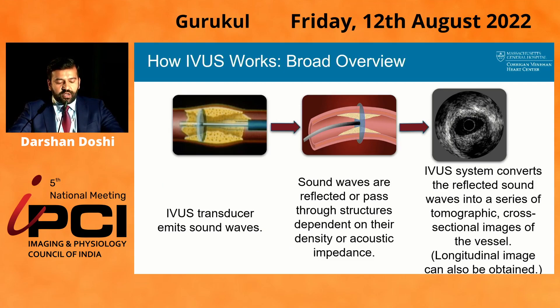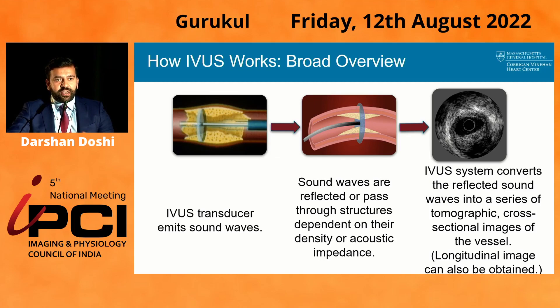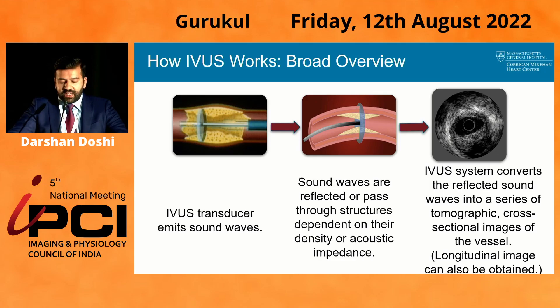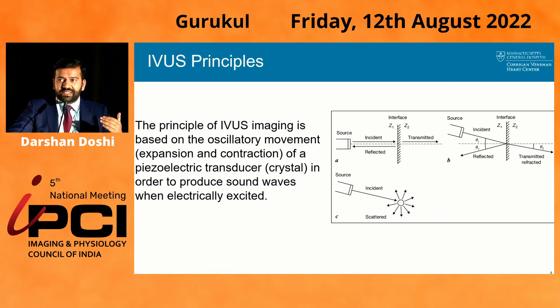On a broad level, how does IVUS work? There is a transducer that creates sound waves. Those sound waves are either reflected or they pass through structures depending on their acoustic impedance. Whatever bounces back is usually bright; whatever goes through and doesn't bounce back is usually darker. The IVUS system then converts those reflected sound waves into a series of tomographic cross-sectional images, which can tell you the makeup of the vessel architecture.